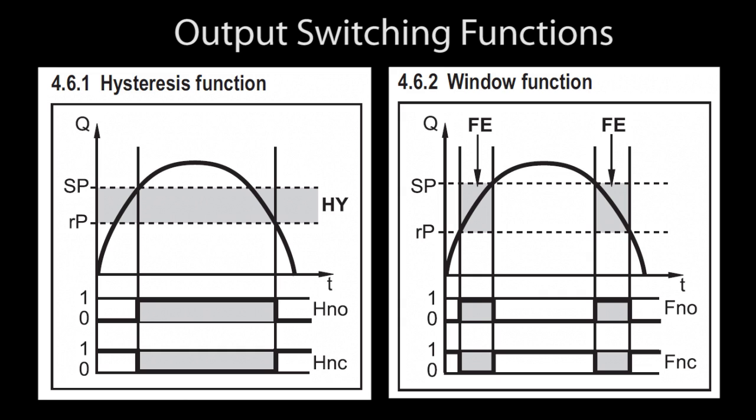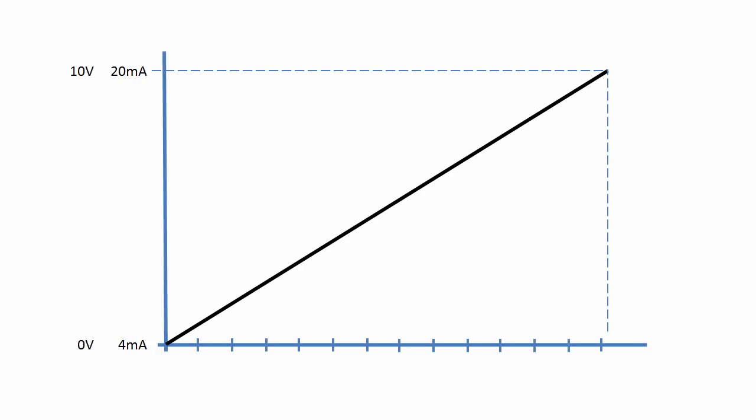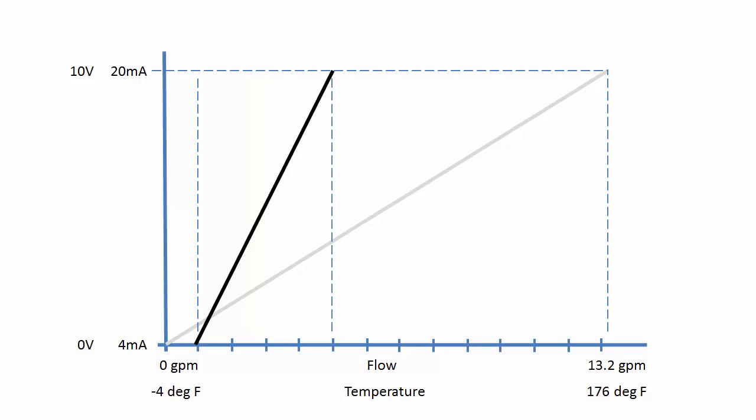Well, that was output 1, so let's do an output 2 parameter setting example. Output 2 is the analog output on this sensor. Normally, the output 4 to 20 milliamps or 0 to 10 volt range corresponds to the max extremes of the flowmeter or built-in temperature sensor. For this sensor, that would be 0 to 13.2 gallons per minute or minus 4 to 176 degrees. If we know our flow rate is going to be between 1 and 5 gallons per minute for example, then we can scale the output to match that so we get to use the full range of output values to represent that 1 to 5 gallons and not be limited to just a small range of values.